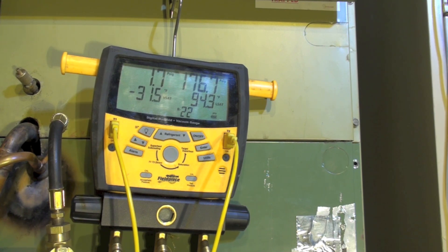What I see is probably a little bit of either valve leakage or maybe there's some more refrigerant coming out of the oil in that accumulator. But that's not a quick equalize. It looks like this thing's pumping pretty well. Okay, we'll call it good on that.